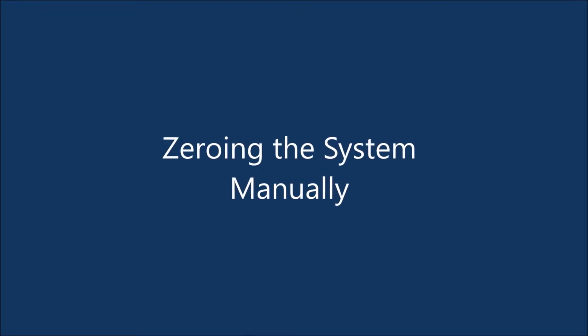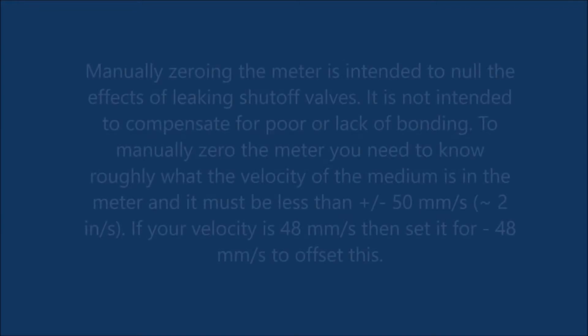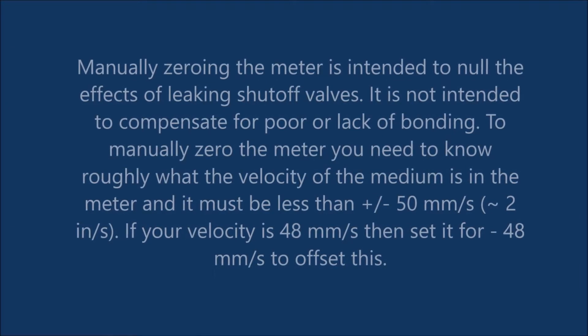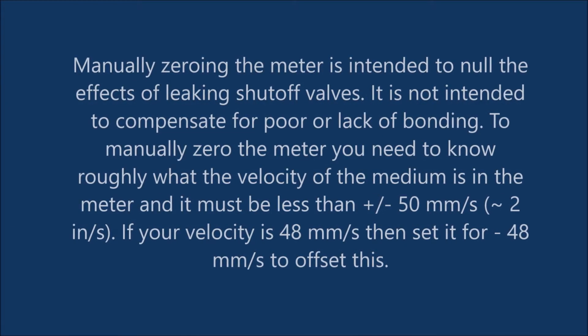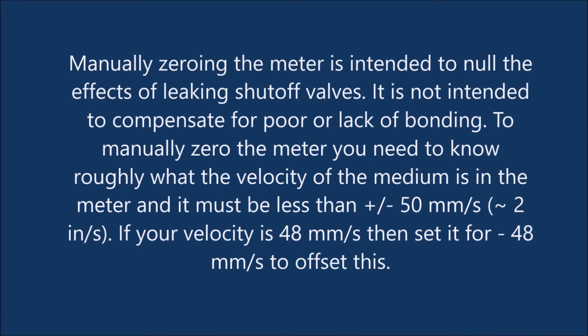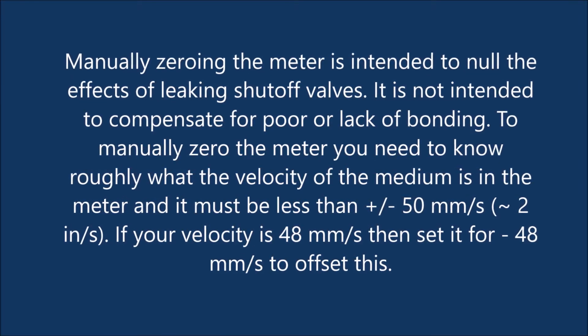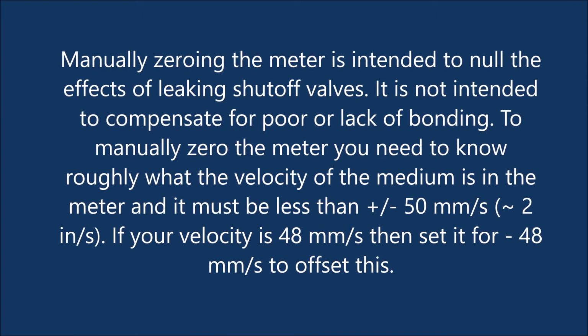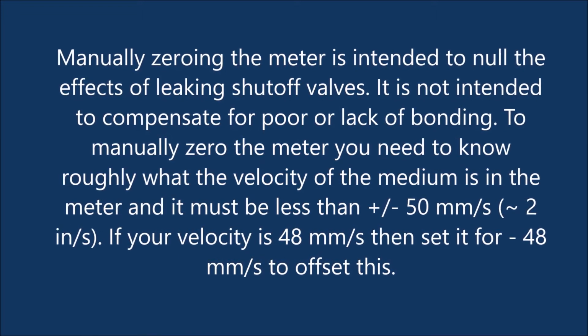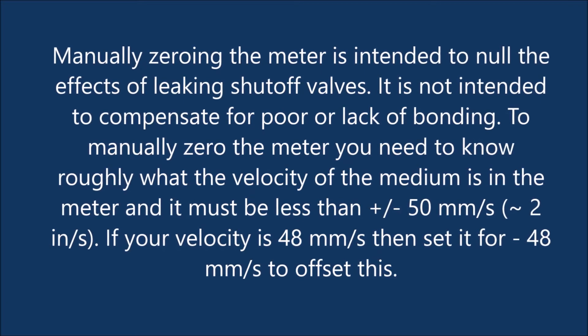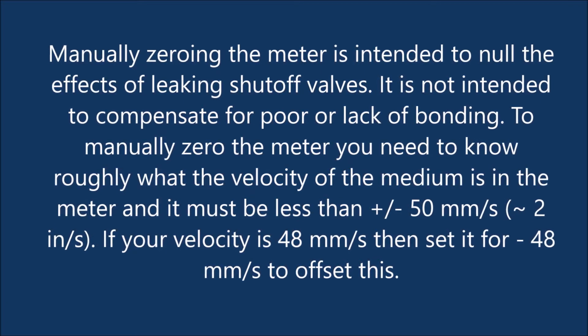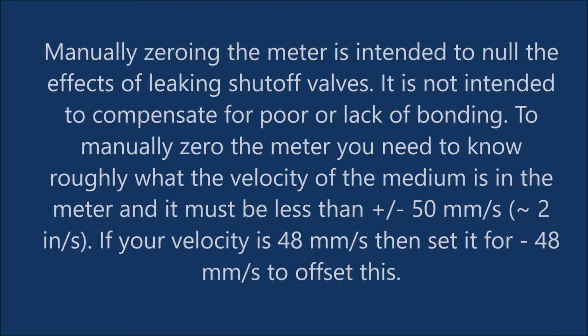Zeroing the system manually. Manually zeroing the meter is intended to null the effects of leaking shut-off valves. It is not intended to compensate for poor or lack of bonding. To manually zero the meter, you need to know roughly what the velocity of the medium is in the meter, and it must be less than plus or minus 50 mm per second, approximately 2 inches per second. If your velocity is 48 mm per second, then set it for minus 48 mm per second to offset this.